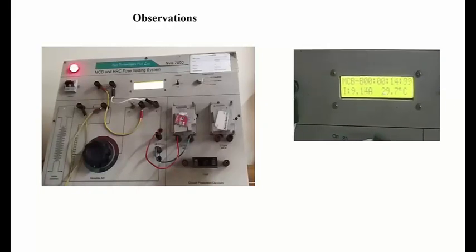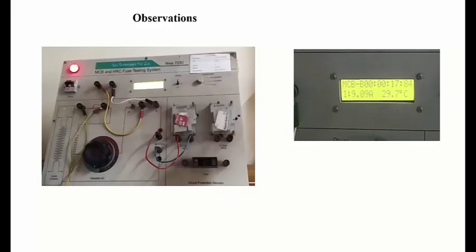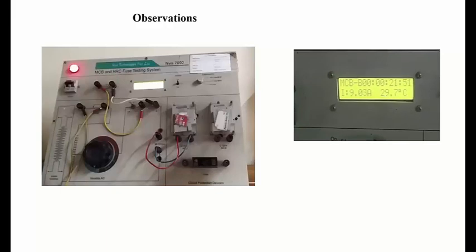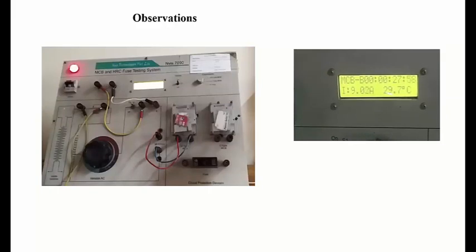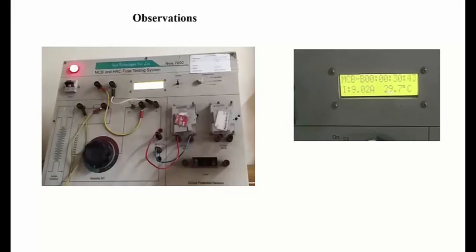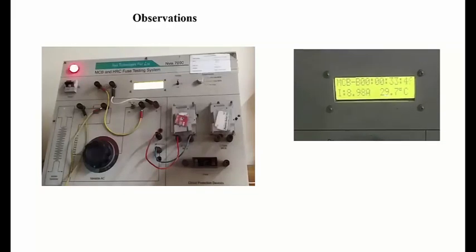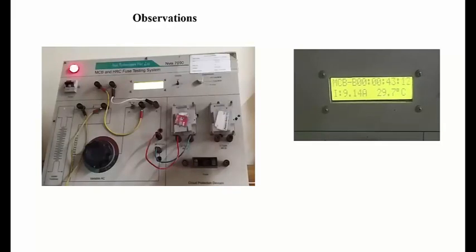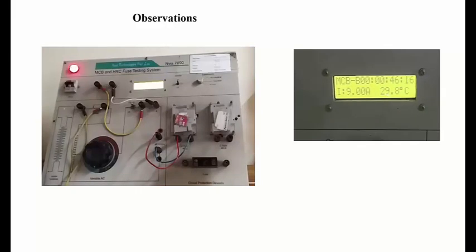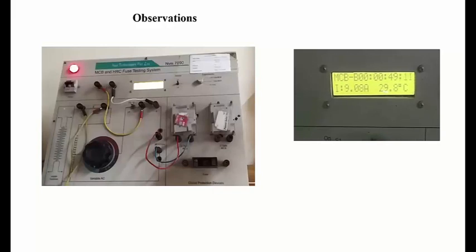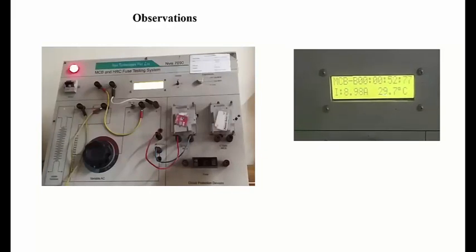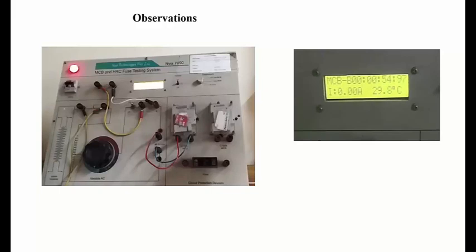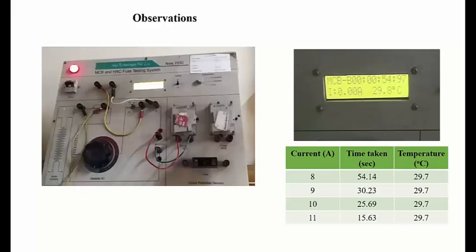We'll be trying to maintain this current at 9 ampere using the rheostat and observe the time when the MCB operates. The temperature is also shown. We'll be noting down the current, the time it takes to operate, and the temperature of the MCB. This is the first set of readings.